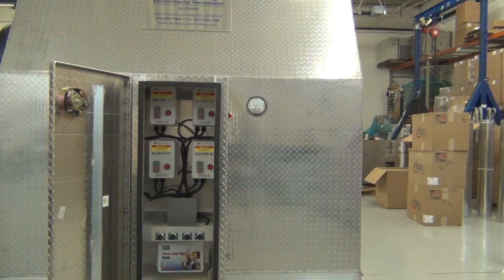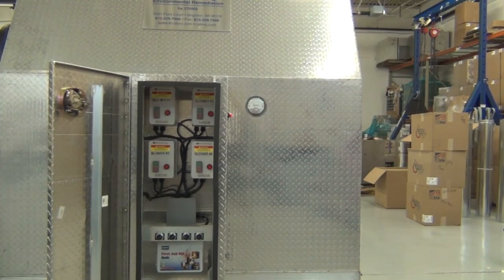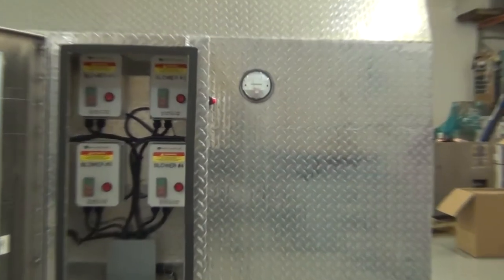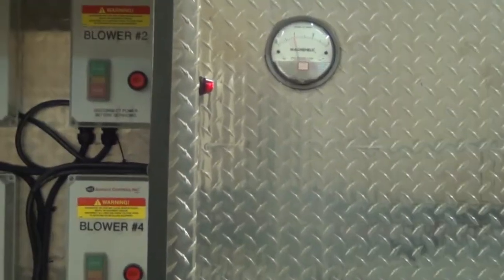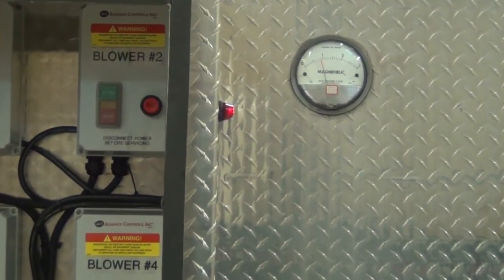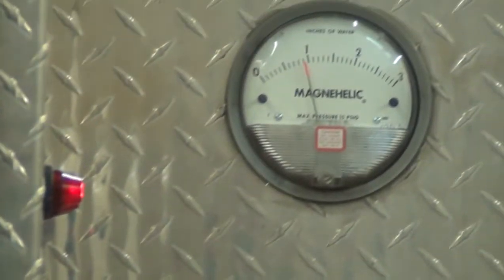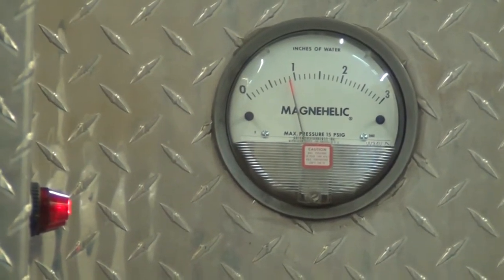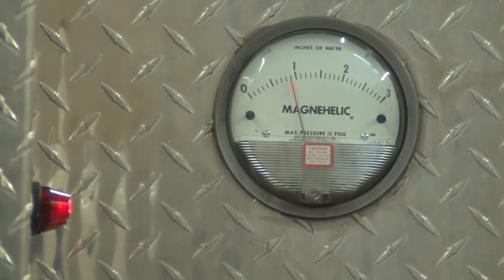We can see the filter loading as it works over time by monitoring the pressure gauge that's located in the front of the system right next to the control panel. With the 2 blowers operating, we're indicating about a 1-inch pressure drop with clean filters. As we load the system more, this pressure drop of course will increase depending on the volume going through the system and the filter condition.